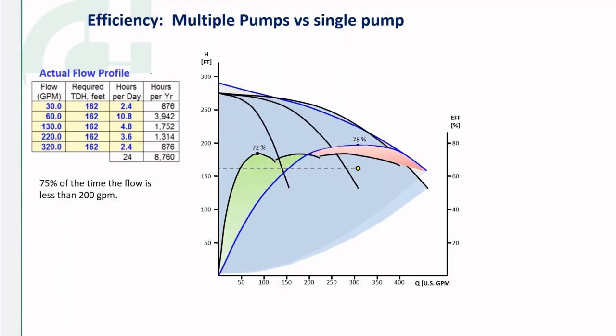I'll give you a hint, 75% of the time, the flow is less than 200 GPM. And then another hint, at 60 GPM, where we spend almost half the day, the triplex system is 25% more efficient. So that's going to add up and provide a significant amount of energy savings. So at the end of the day, it's the area under the curve multiplied by the time spent at that point.